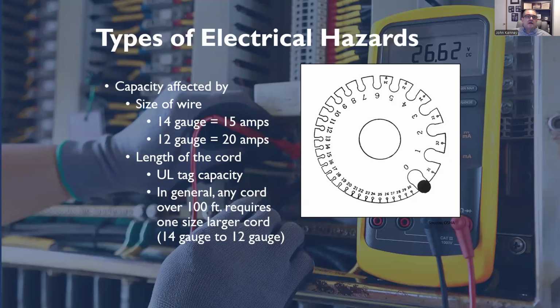Types of electrical hazards. Capacity is affected by the size of the wire, like 14 gauge is for 15 amp service, 12 gauge is 20 amp, the length of the cord, and the UL tag capacity. In general, any cord over 100 feet requires one size larger cord, 14 gauge to 12 gauge. So what does that mean in a real life example? You're not going to be able to put two 14 gauge 100-foot cords together, okay? It's going to create a problem, can possibly create a short and overload and many other issues. So you would then go to the next gauge lower of 12 gauge and so on and so forth, which is why we do not recommend adding a bunch of cords together, and keeping the source, like your portable generator, within range to make things easier and safer.